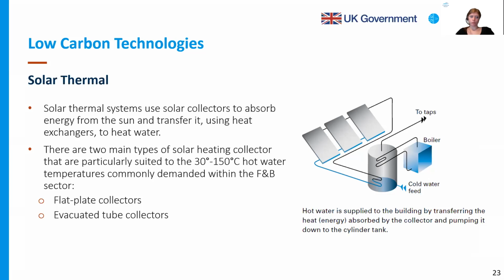So there are 2 different types of thermal energy collectors. So flat plate collectors are ready to implement, low cost, low maintenance systems. The catch is that they are only suitable for heating water in the range of about 30 to 80 degrees Celsius. If that is the range of hot water temperature that you're looking at, this is a readily available solution that is also simple to implement and operate. And the maintenance aspect is also very negligible. So the thermal efficiency of the flat plate collectors is typically around 70%. But yeah, solar energy is free, right?